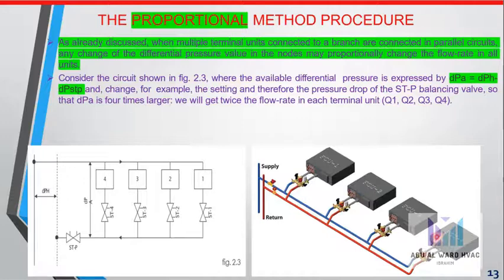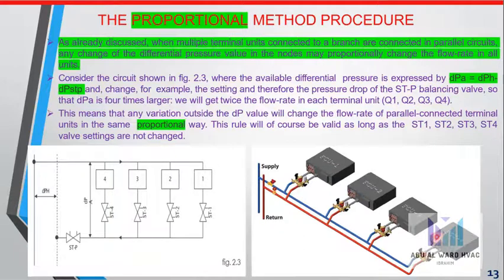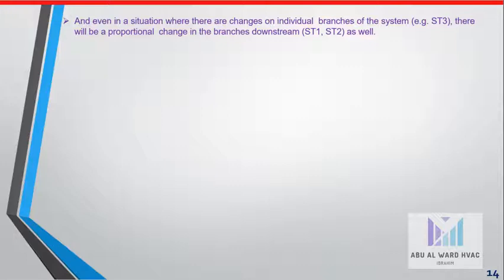If the DP_a is four times larger, we will get twice the flow rate in each terminal unit Q1, Q2, Q3. This means that any variation of the DP value will change the flow rate in parallel connected terminal units in the same proportional way. This rule will be valid as long as the valves remain set. Even in a situation where there are changes on individual branches of the system, like ST3, there will be a proportional change in the branches downstream ST1 and ST2 as well.